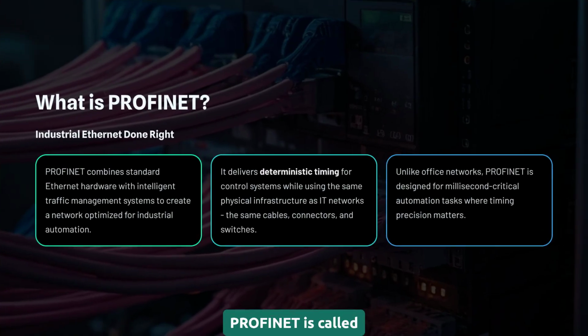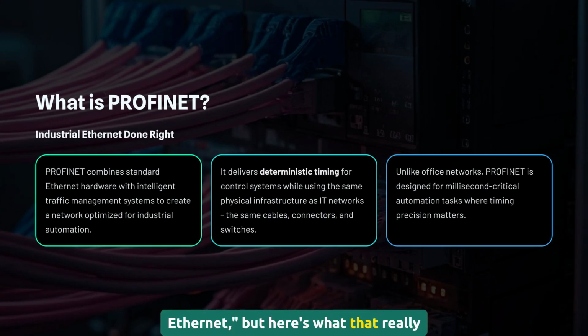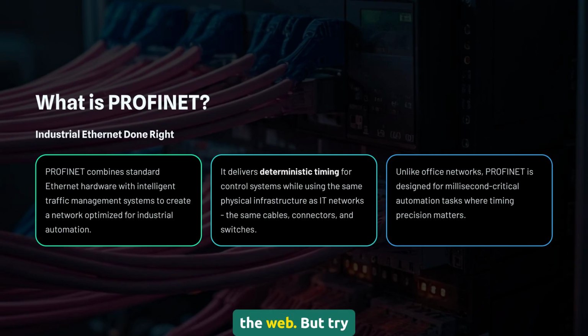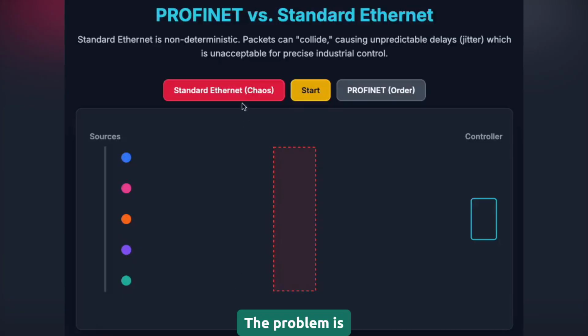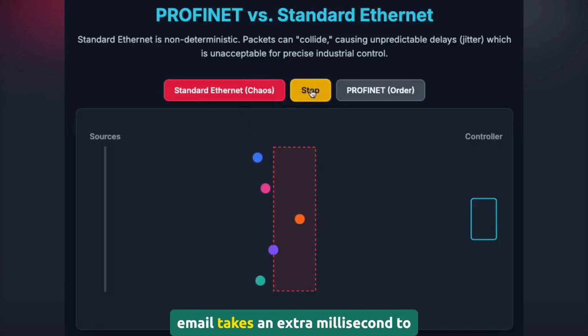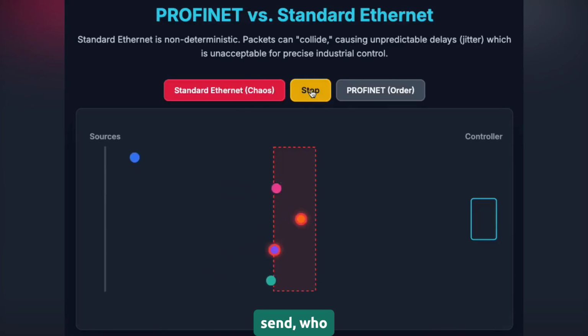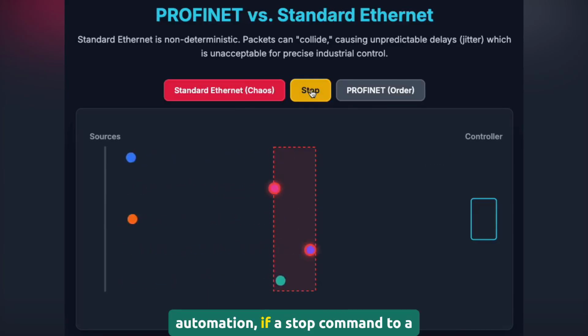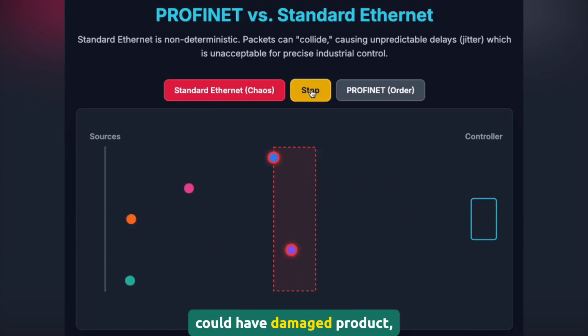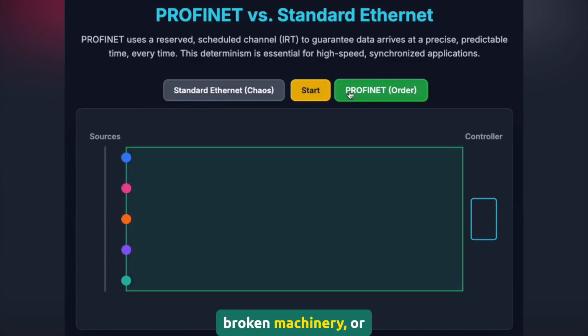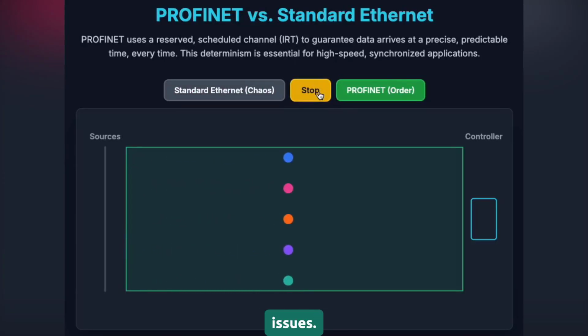PROFINET is called Industrial Ethernet, but here's what that really means. Regular Ethernet, the stuff in your office, works great for sending emails and browsing the web, but try to control a high-speed packaging line with it, and you'll have chaos. The problem is timing. In the office, if your email takes an extra millisecond to send, who cares? But in automation, if a stop command to a servo motor is delayed by even a few milliseconds, you could have damaged product, broken machinery, or worse, safety issues.